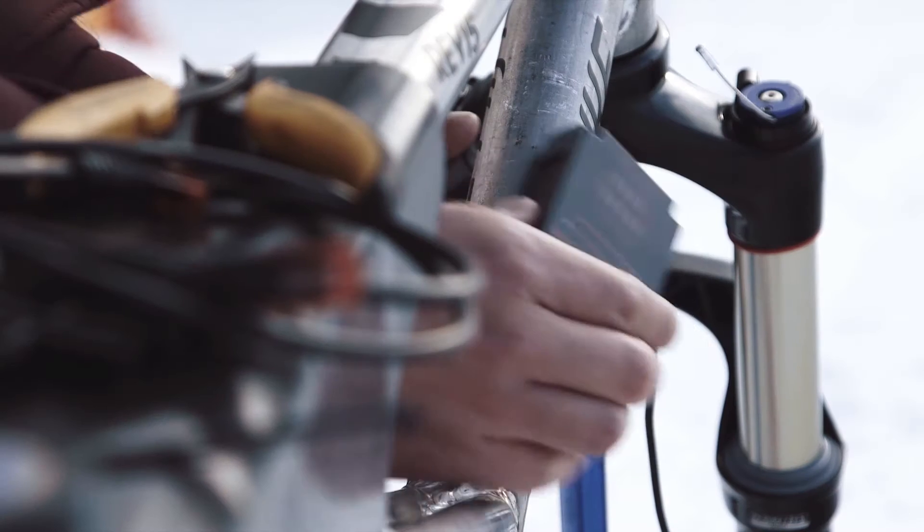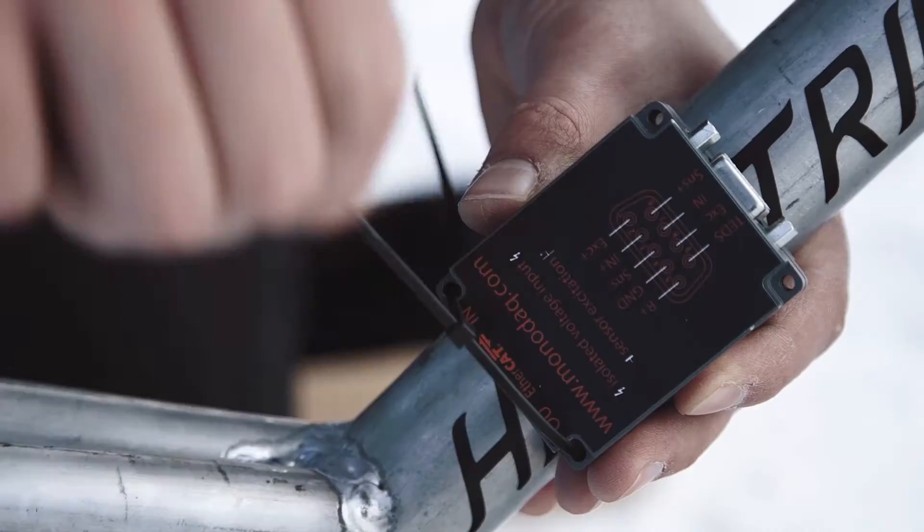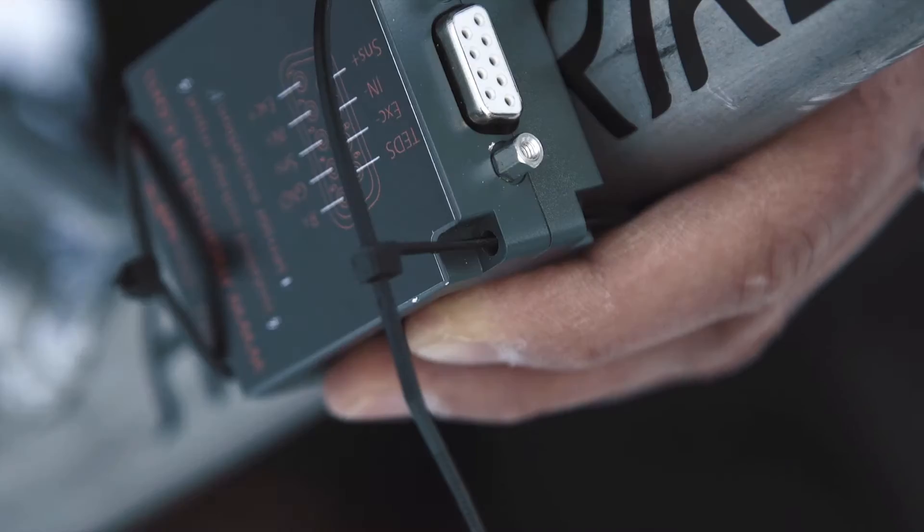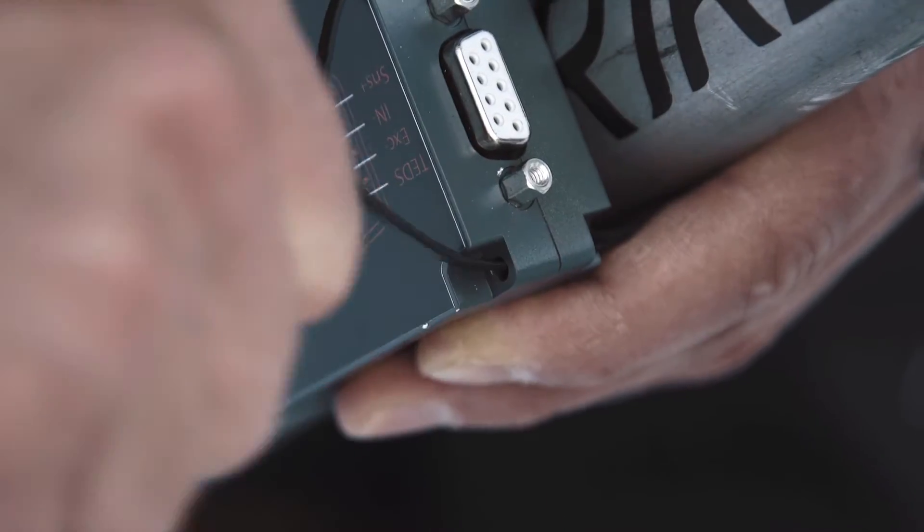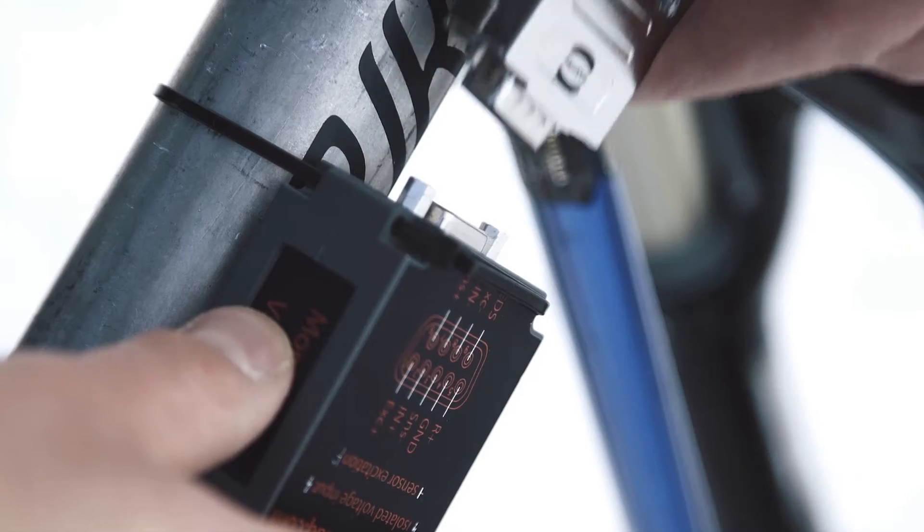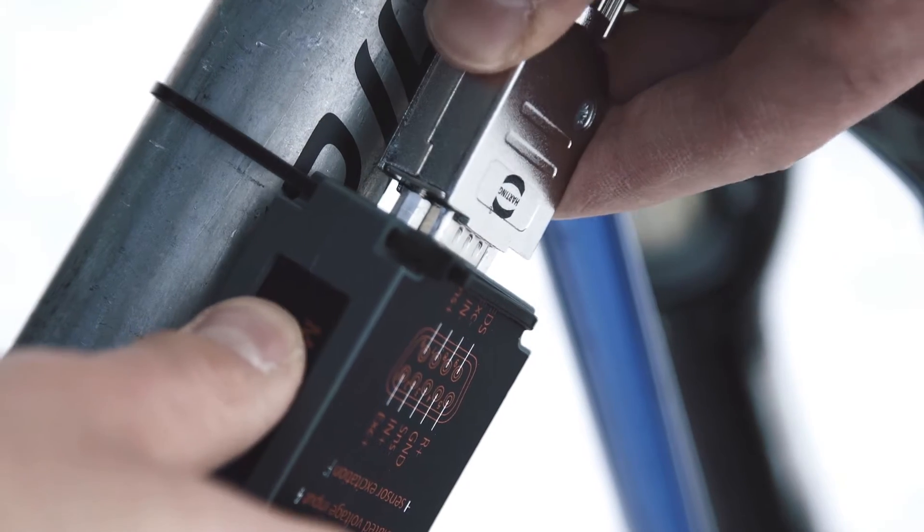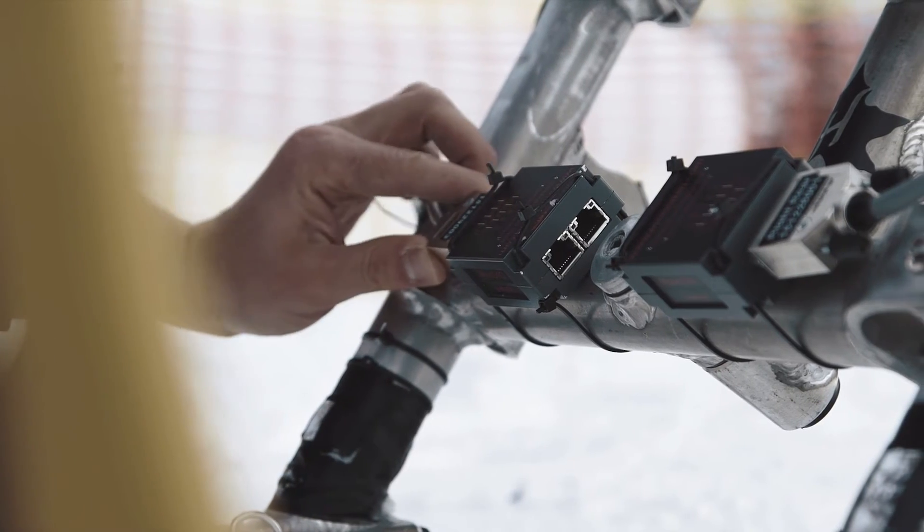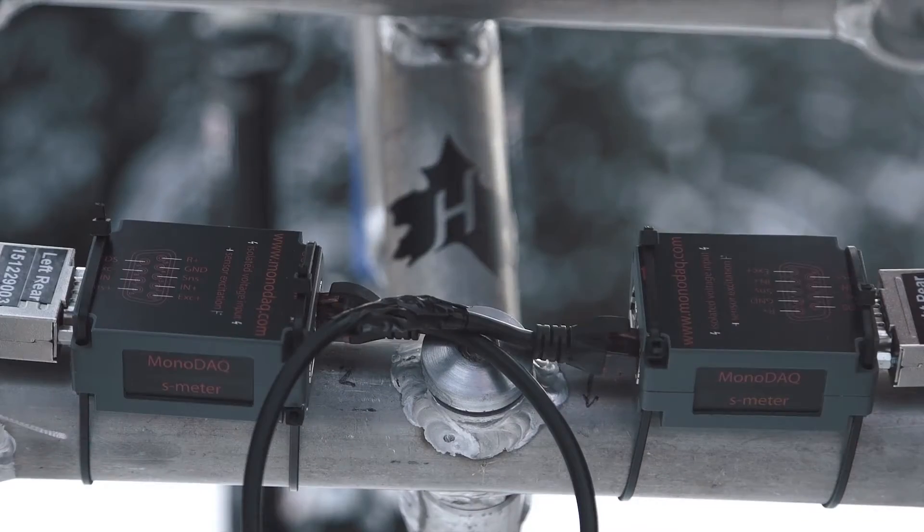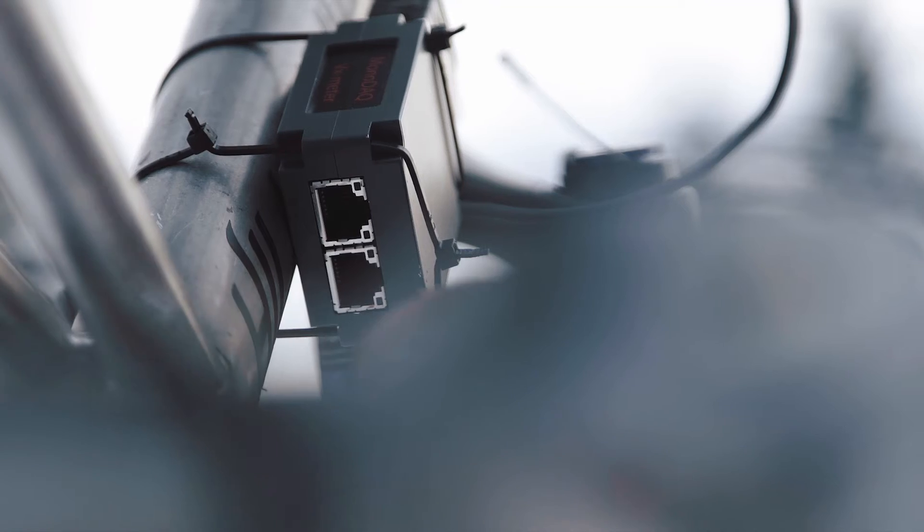We are presenting the MonoDAQ Sensor Interface, a single channel data acquisition instrument. Due to the small size, MonoDAQ makes it possible to install very short analog cables, reducing the signal noise and cabling cost.